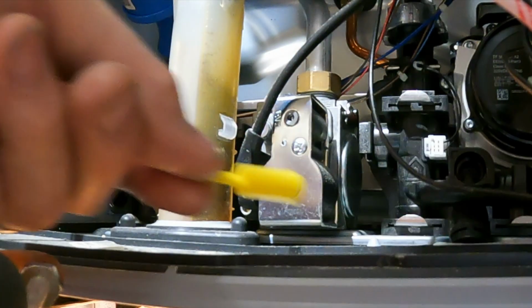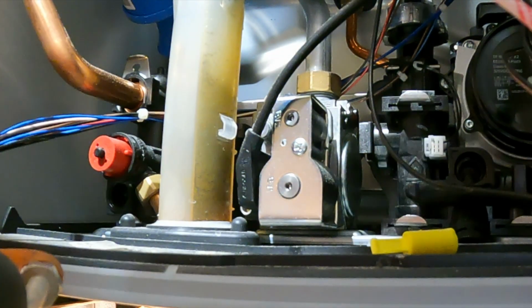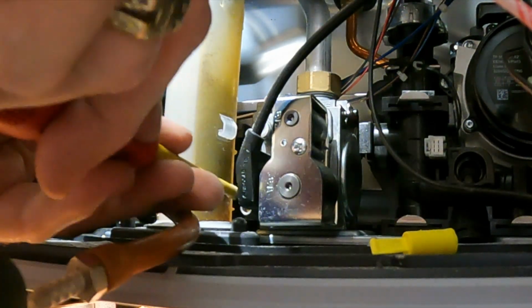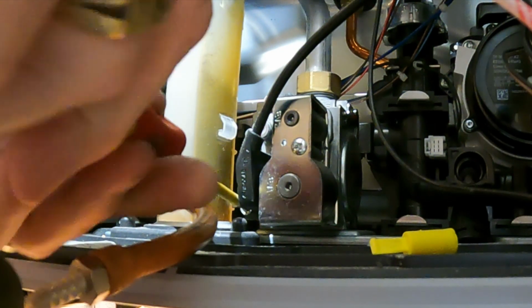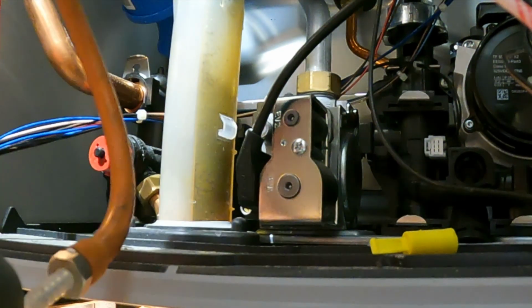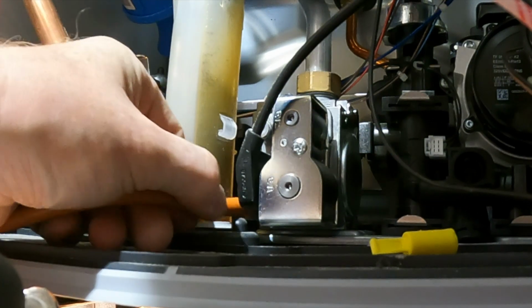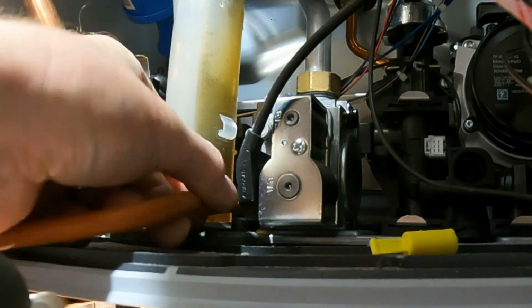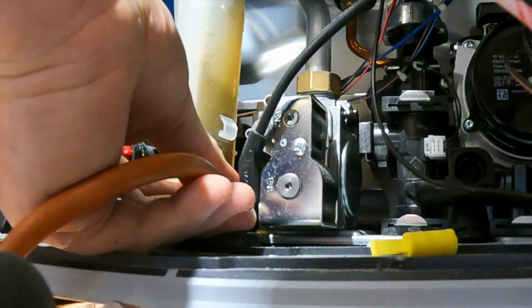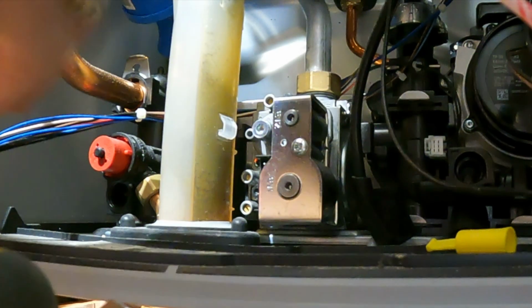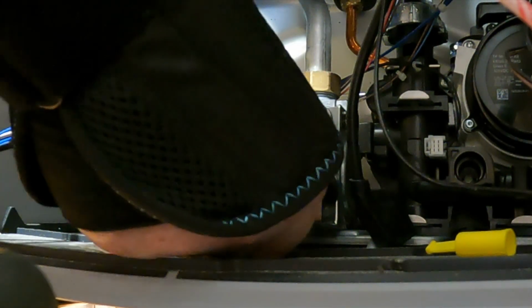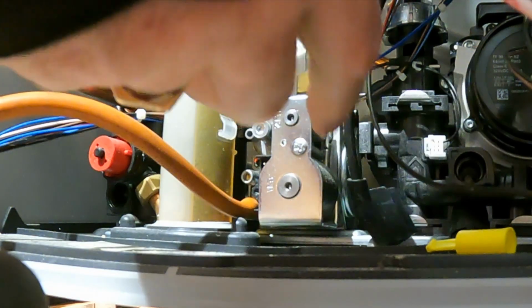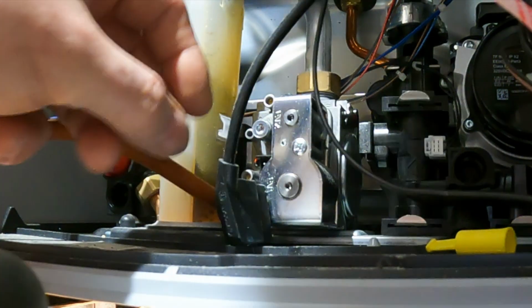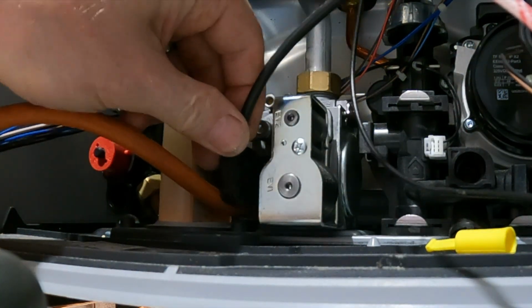Now behind this little yellow cap is the inlet test screw. So I've got my digital manometer connected. I'm just going to loosen this screw and then connect on. Now if you are struggling to get it on, you can remove the power to the gas valve and then you should be able to slide it on and then put your connector back in for your gas valve.